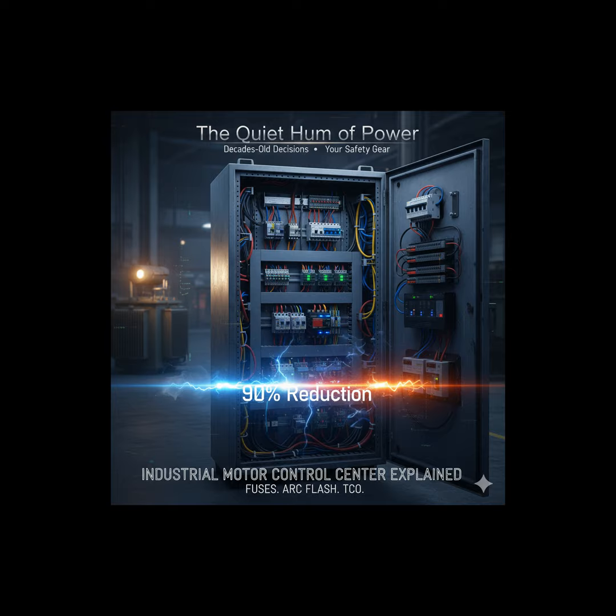So what does this all mean then? The Motor Control Center is far more than just a big metal box. It's a highly engineered, standardized ecosystem built on 3 core pillars: centralization for efficiency, component integration via the combination starter, and robust protection defined by NEMA, UL, and the NEC. And I think the key takeaway is that when you're dealing with industrial control, performance and safety are just inseparable. Understanding the physical strength of the bus bracing and the environment-specific enclosure is just as critical as understanding the sophisticated control logic running inside those units, the VFDs and the solid-state relays.